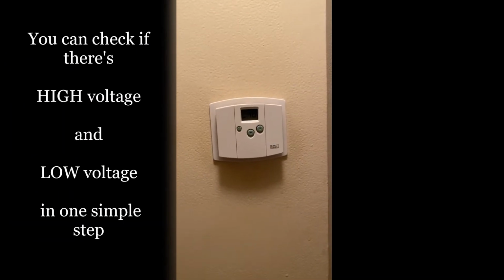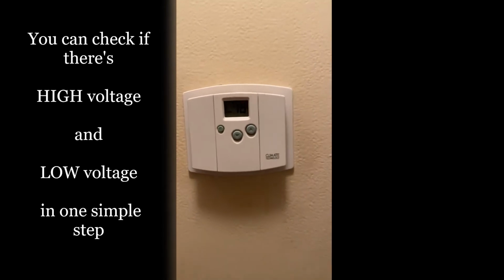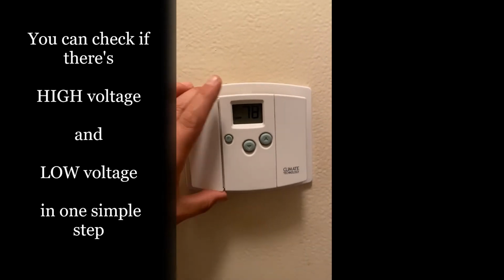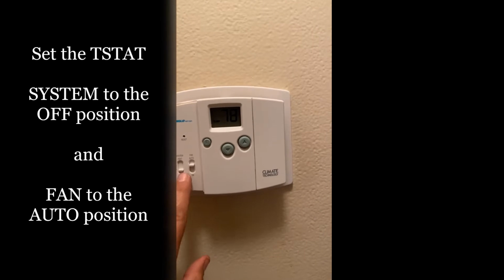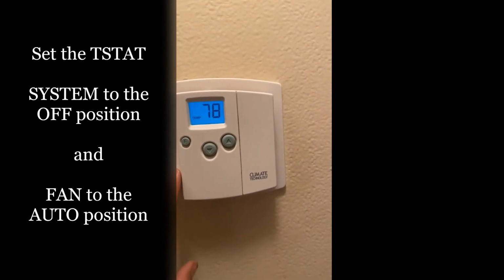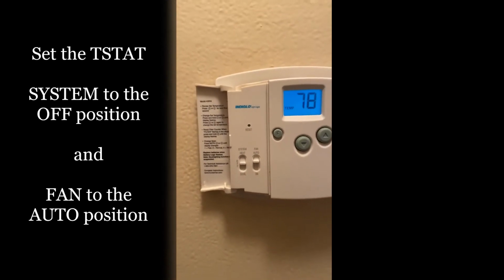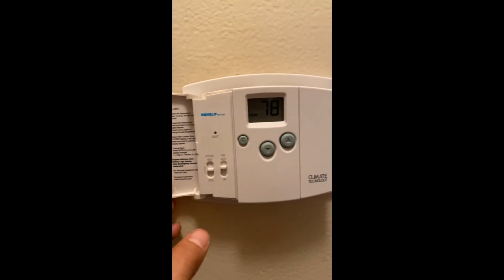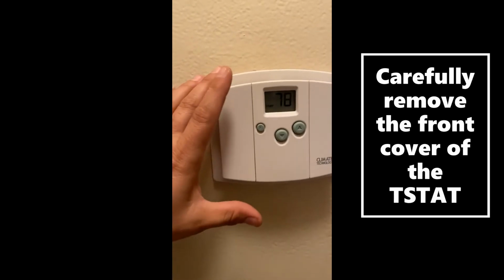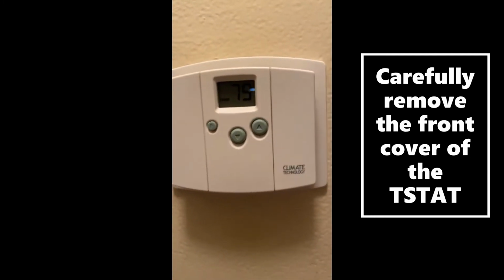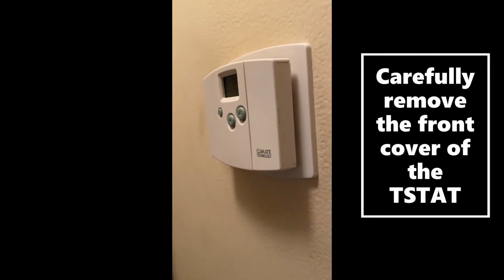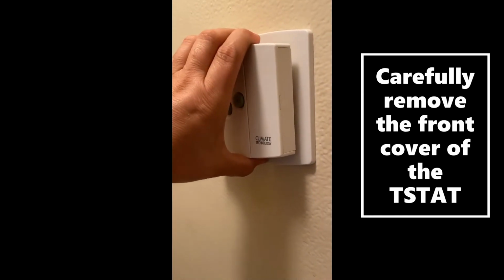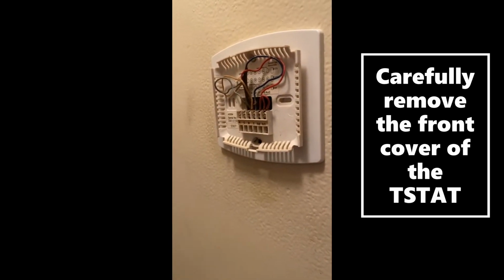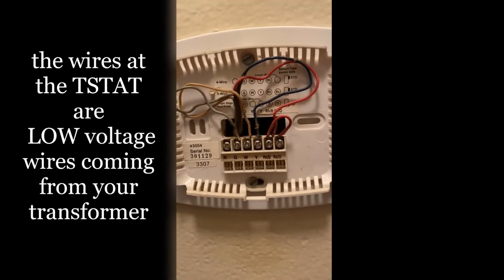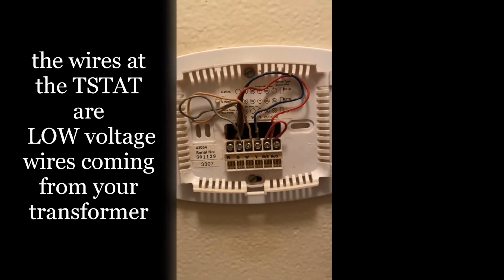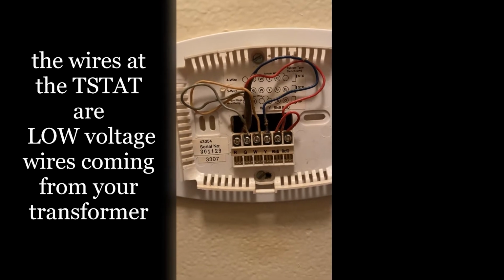So we can check if we have high voltage and low voltage at the same time by doing something simple. You set your system to the off position, fan to auto. And we're gonna pop off the T-stat. Most of them are pretty easy, they come right off, with a little pull like so. And then we're gonna look at our wires here. This is your control voltage, or your low voltage is what you're gonna find here.